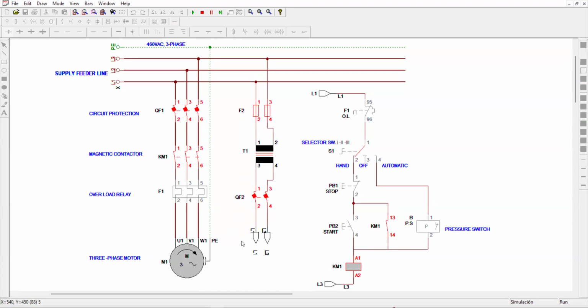Once you activate the manual position in the selector switch, the circuit allows you to override the input devices and control the motor directly. Whereas if you rotate the selector switch to the off state, the motor will turn off. The motor will de-energize. If you turn the selector switch to automatic, since our pressure switch is in a normally closed state, it automatically runs the motor without manual intervention.